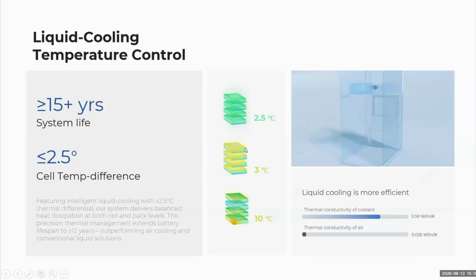And also with the Sungrow cooling machine, we can control the battery cell temperature difference to less than 2.5 degrees. We also have a pipe under each battery module. There's a cooling pipe, and we also optimized the cooling solution: at the beginning the cooling liquid has better performance, so the size of the cooling pipe will be a little bit smaller than at the end of the cooling liquid pipe. So from the beginning until the end, the cooling liquid has the same performance to keep the battery cells at the same temperature.